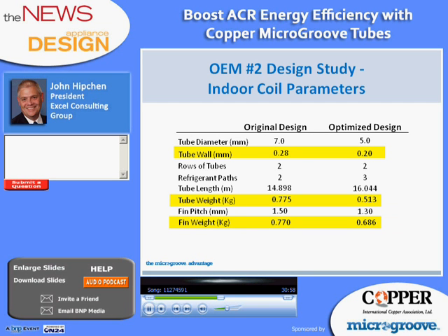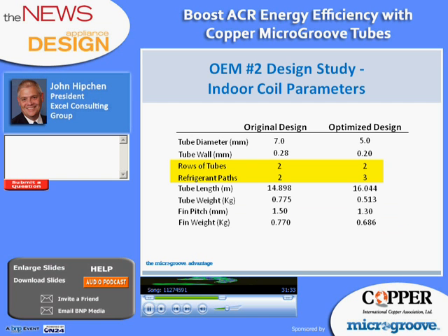Notice here that the optimized evaporator coil goes from 7mm tubes down to 5mm, but does so with more total tube length. But once again, due to the lower weight of the 5mm tubes, there's a weight savings of 262 grams per coil. A smaller fin pitch means a denser coil, but the weight savings in aluminum fin material indicates we've probably got a more compact coil. Our optimized design in this case only has one more refrigerant path than the original and maintains the same number of tube rows.